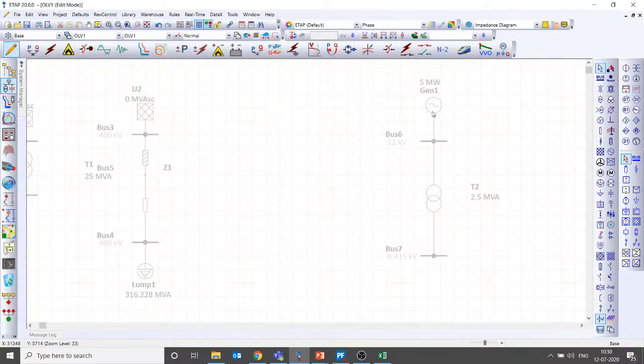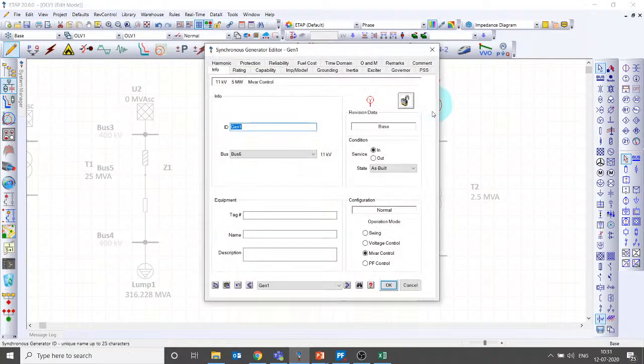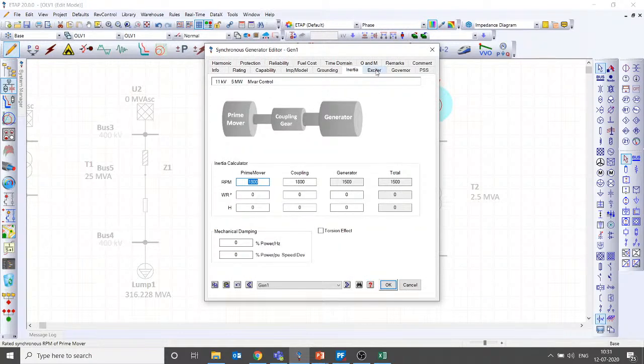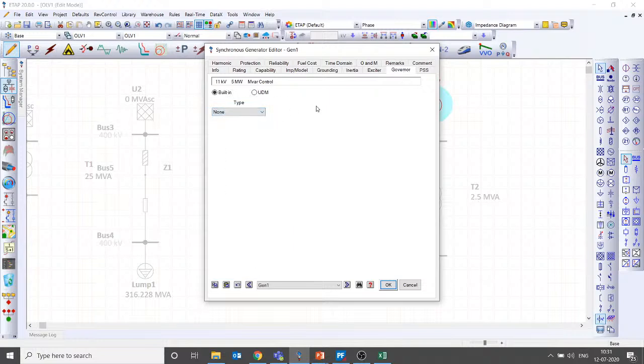Let's talk about this in two ways, Parthiban: one is what happens in simulation, the second is what happens in real time. In real time, voltage control mode is something different, where you fix real power and voltage. But when you have only one generator feeding the loads without a grid connection, you cannot operate in that real power control mode. You cannot fix P, because you need to adjust your real power generation to match the demand each and every moment. That is called isochronous mode. So when you run generators in islanded systems, that is, when it is the only generator, you have to operate it in isochronous mode.